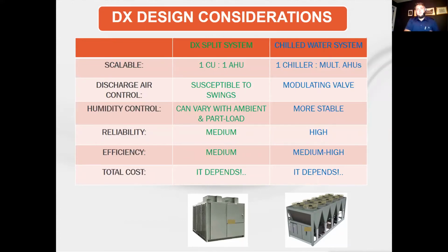So it's always worth looking at why did you go DX originally, and maybe worth a final comparison, because when you compare some of the newer systems of packaged chilled water plants that are available now from all different kinds of manufacturers, even with pump packages, it starts to almost look very similar to if you purchased a DX split system, with condensing unit and indoor coil. So it's good to weigh the pros and cons, especially with the new technology of both types of systems, and really make sure that you're picking the right system for the application that you're looking to do.